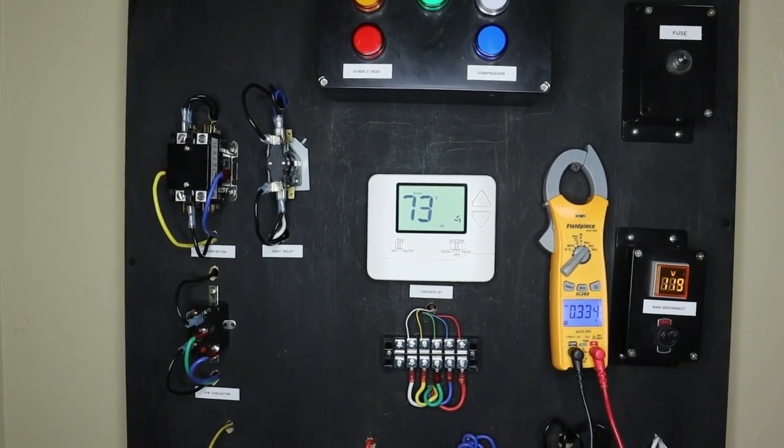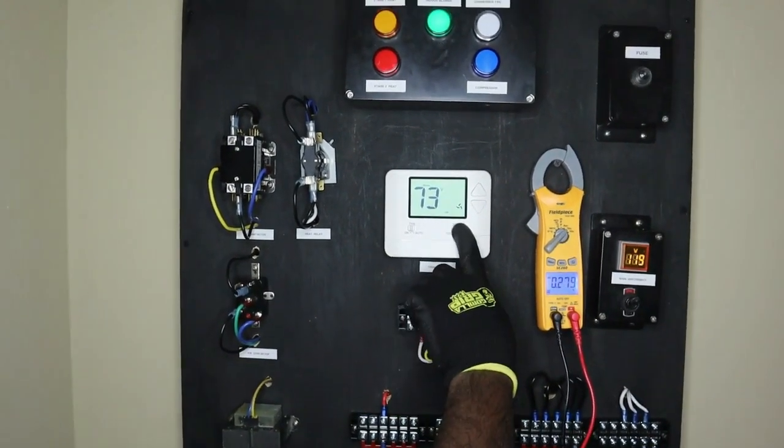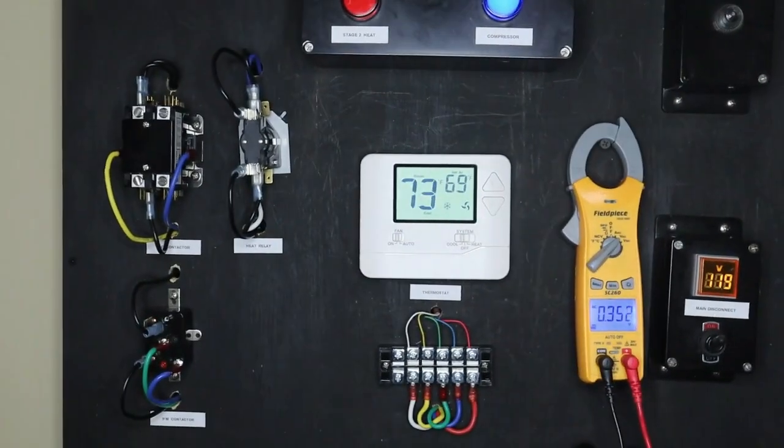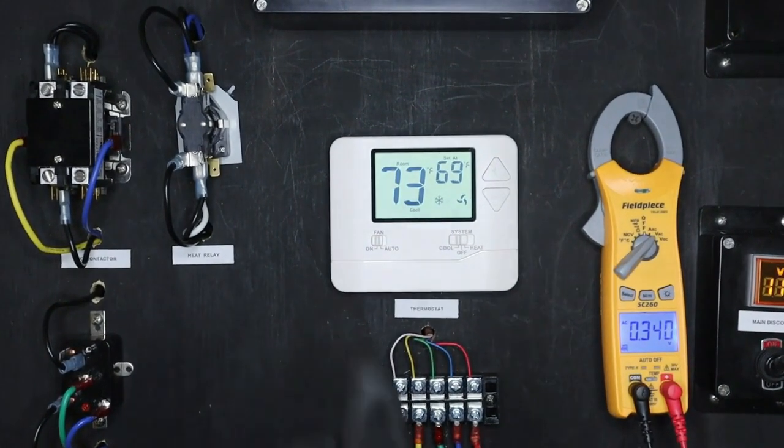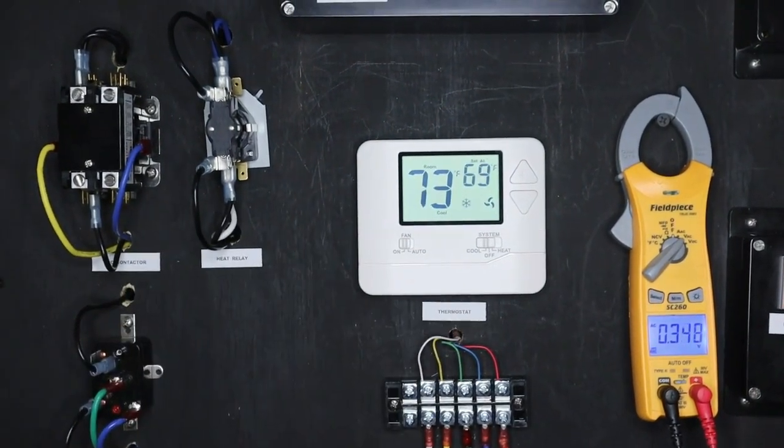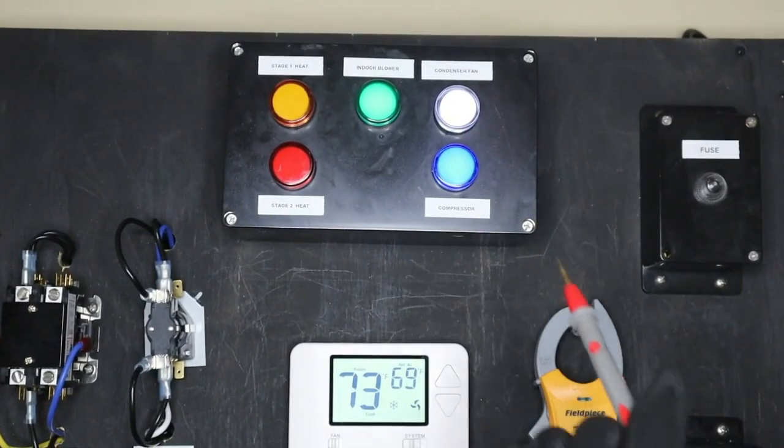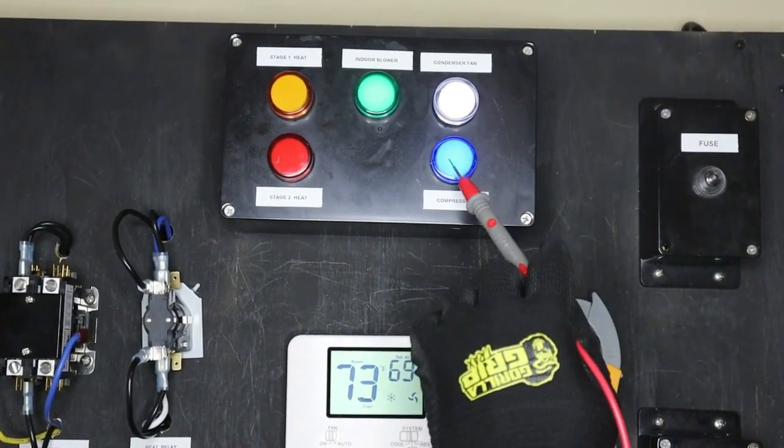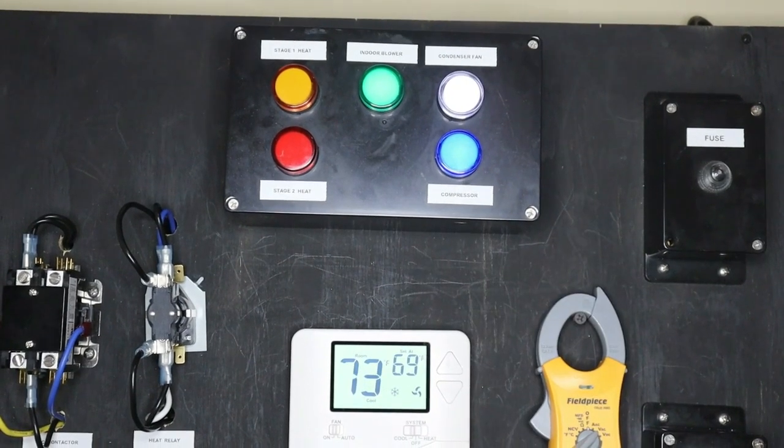So now if we were to call for cooling. So I would turn this to cool. As you just heard our contactor pulled in. Now you see our condenser fan LED is lit. Our compressor LED is also lit.